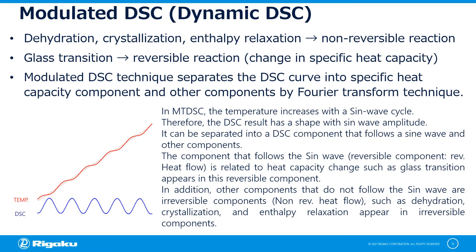Since the glass transition is small, it often overlaps with other reactions and disappears. For example, dehydration, crystallization, and enthalpy relaxation can be considered as phenomena that may overlap with the glass transition. When these reactions overlap with the glass transition temperature, the glass transition is measured by changing the sample pan or measuring a second run, but dynamic DSC, which is a modulated DSC, is also an effective means.